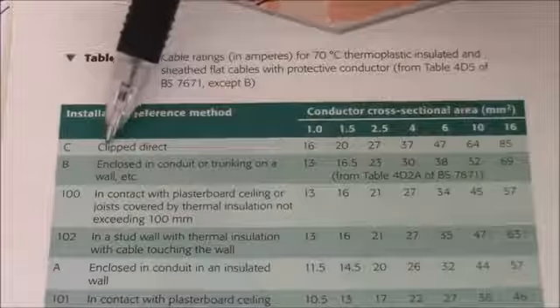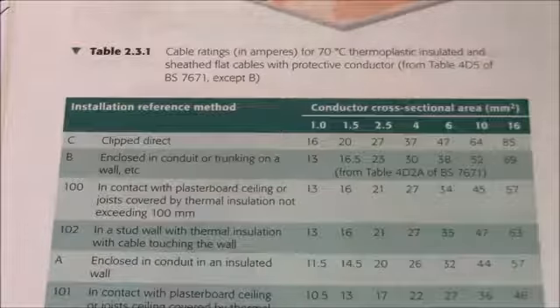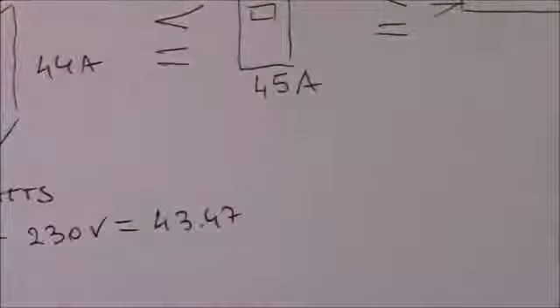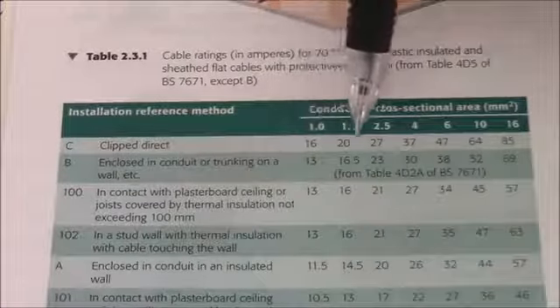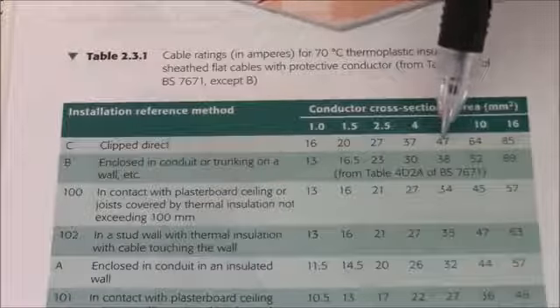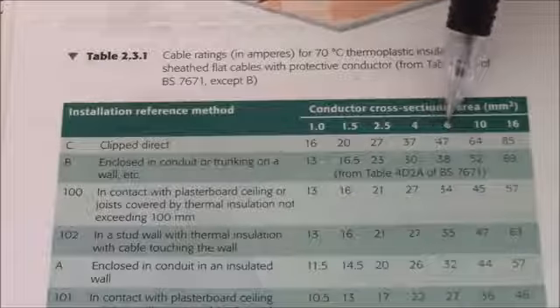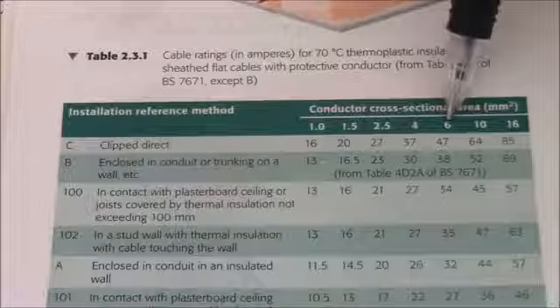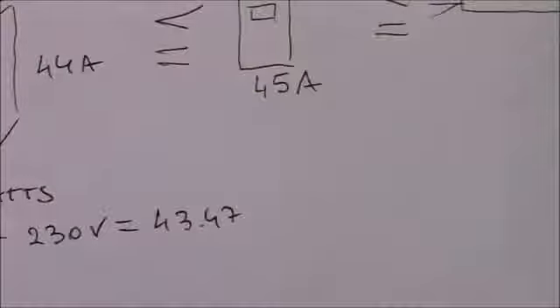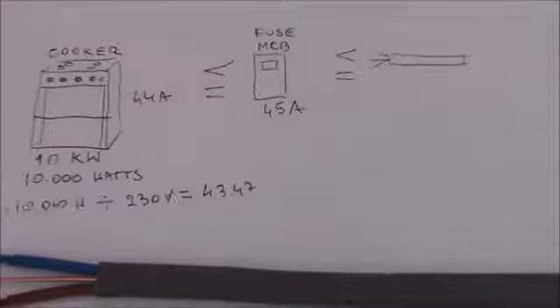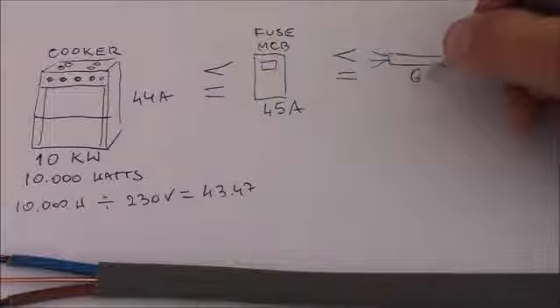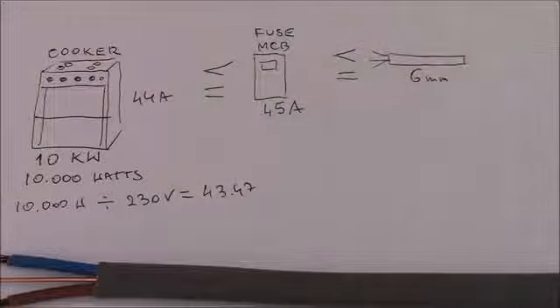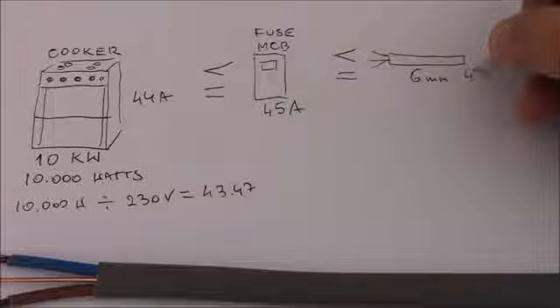We need to use this book again. So we know how we install it. Let's say we clip direct to the wall. If we say that this has to be equal or bigger than 45 amps, let's have a look at the first column. 47 amps is bigger than 45, so that's the size of the cable, 6 millimeters. So we know that this cable should be 6 millimeters minimum, as it's rated 47 amps.